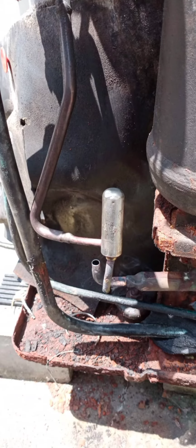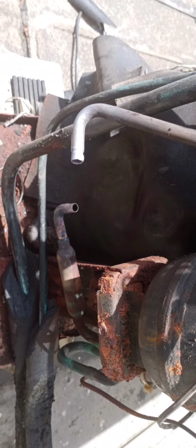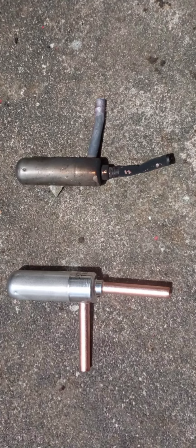So we checked the Daikin E9 error code, and the expansion valve is faulty. Some of the expansion valve near the leaking also. So we propose to replace the expansion valve. We propose to replace it with a new expansion valve. This job we have already done.